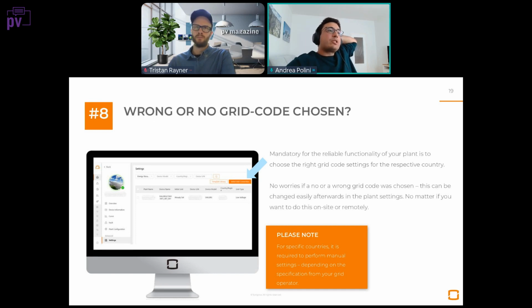So you must first select the inverter and then do the initial grid connection, and there you can select which country it is and some additional options. For example, if the backup mode is being used or if the VDE limitation is being used. Then once it's over, the inverter will disconnect from the grid, wait a few minutes, run some more self-tests, and then reconnect to the grid.